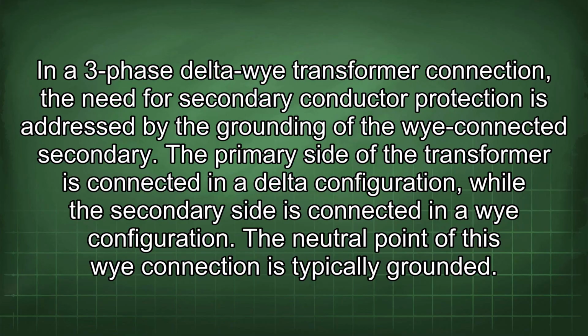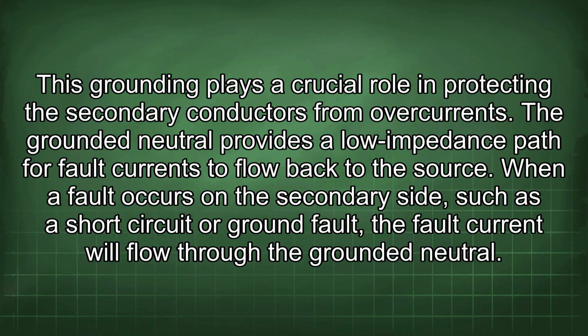In a three-phase Delta-Wye transformer connection, the need for secondary conductor protection is addressed by the grounding of the Y-connected secondary. The primary side of the transformer is connected in a delta configuration, while the secondary side is connected in a Y configuration. The neutral point of this Y connection is typically grounded. This grounding plays a crucial role in protecting the secondary conductors from overcurrents. The grounded neutral provides a low impedance path for fault currents to flow back to the source.